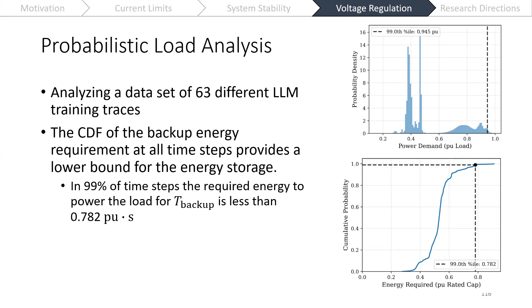Next, to actually find how that buffer from our predictor's error needs to be designed, we look at testing this predictor over all those data sets as well, finding what these errors are between the predicted and the actual load at each time step, and then looking at the cumulative density functions here to find the point at which 99% of our errors would fall below that point, and we use that as our buffer on those lower limit values that our prediction provides. Applying these and looking at the simulation results, we can see that our model predictive control approach can achieve a much tighter regulation on our active power values, which ends up resulting in a tighter regulation on our voltage values.